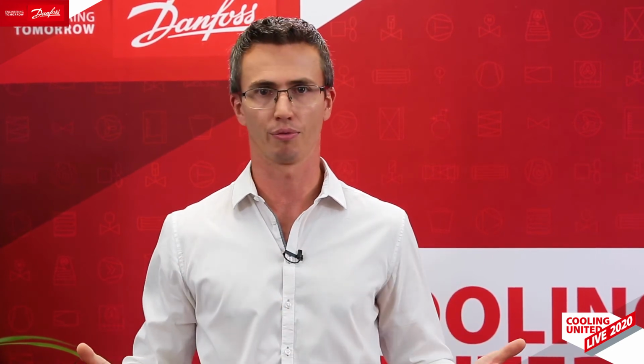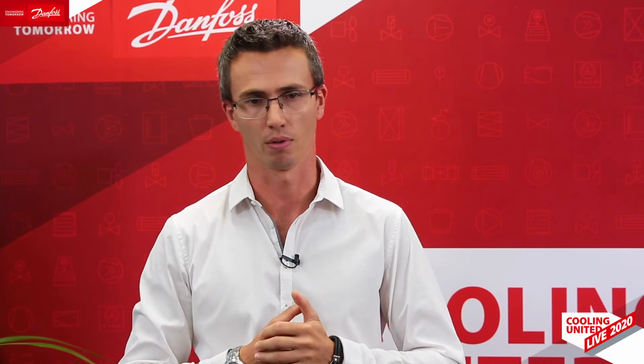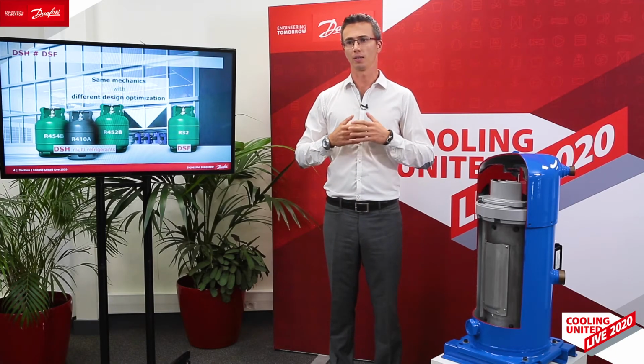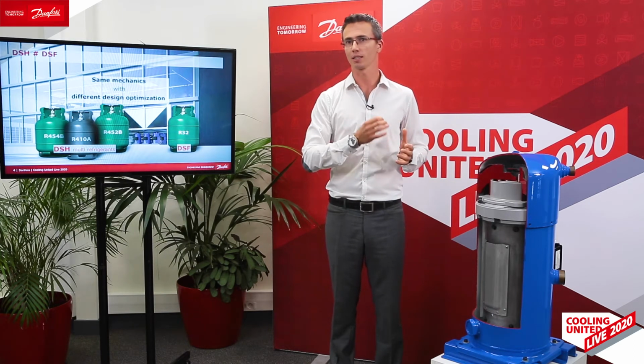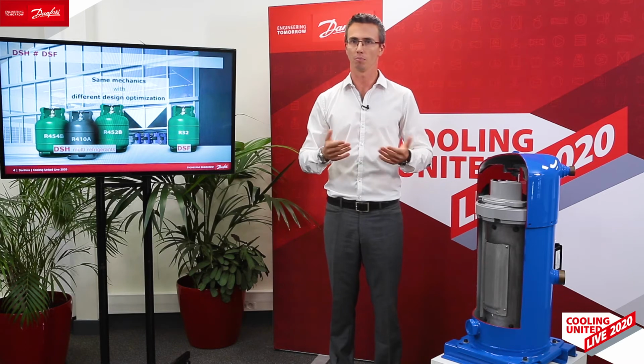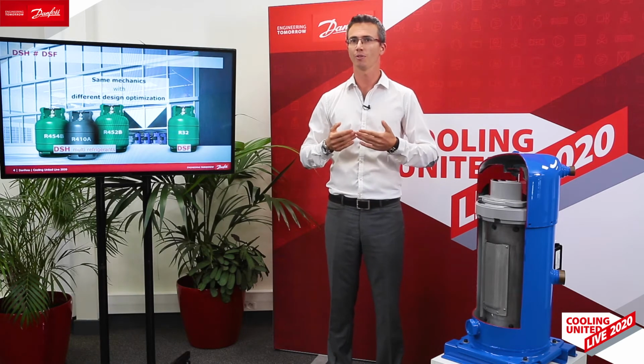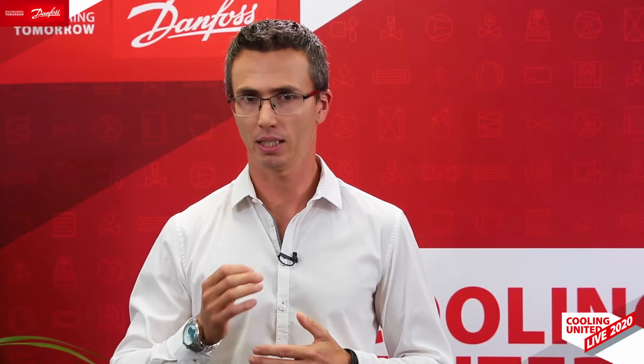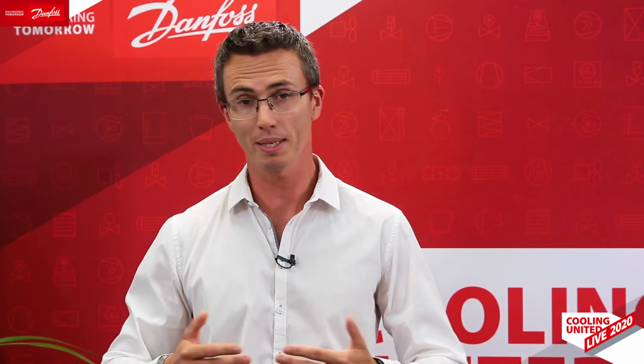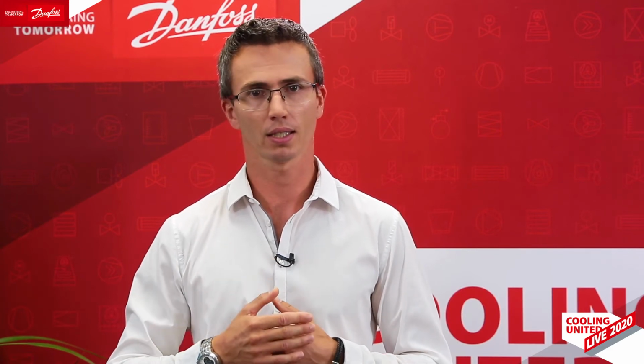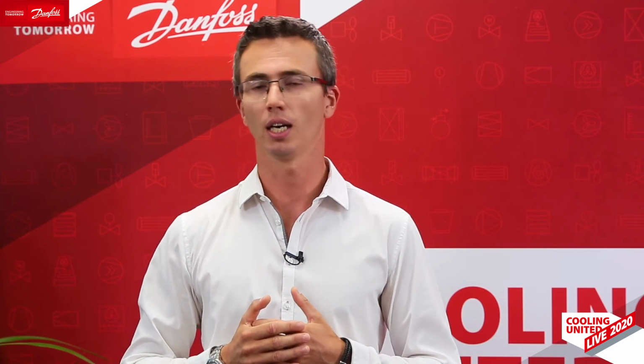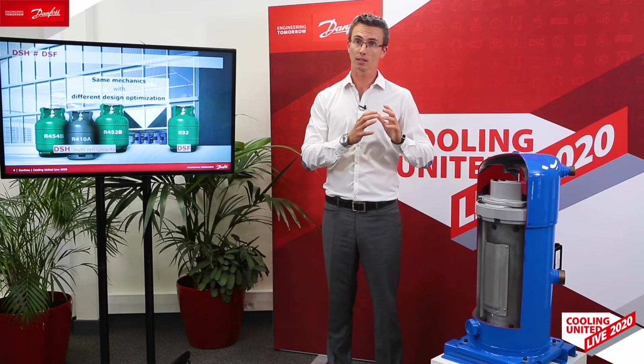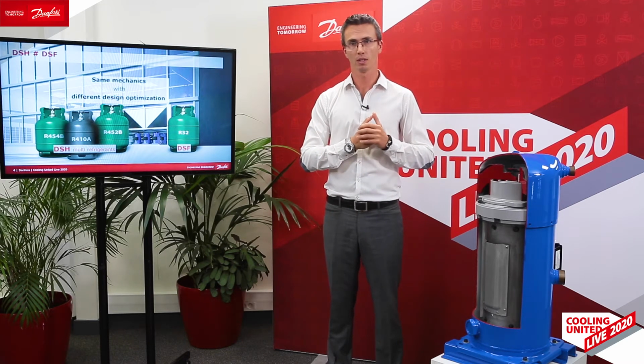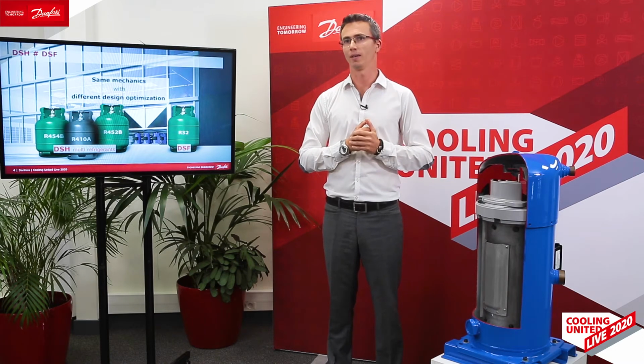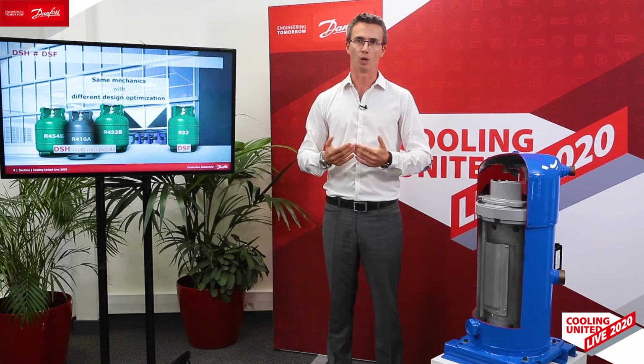First, we have DSH. Its advantage is definitely to be multi-refrigerant: R410A, R452, R454. Thanks to that, and because capacity and performance are extremely close, and because oil is the same and behaves in the same way, it will make for you an easy drop-in solution. That means it reduces to a minimum your R&D investments, and that also means you will reduce the project time to market. For instance, it's also one single range of compressors, which means a very late line customization, and finally, low inventory for you.